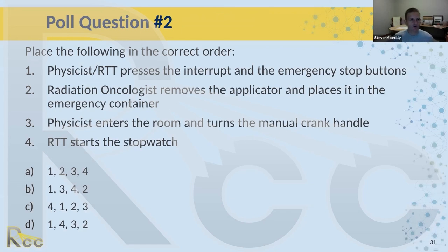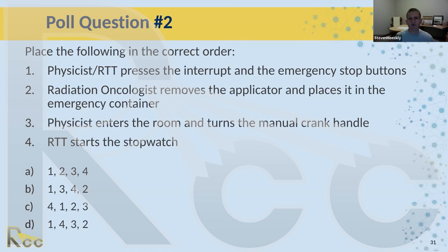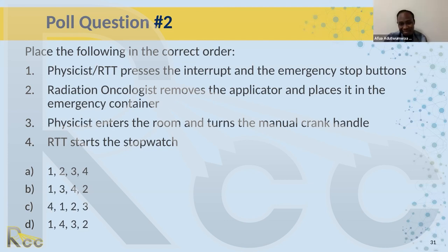Poll question two: place the following in the correct order for an emergency situation — A: physicist or radiation therapist presses interrupt and emergency stop button; B: radiation oncologist removes the applicator and places it in the emergency container; C: physicist enters the room and turns the crank; D: radiation therapist or nurse starts the stopwatch. Think about what order these things would happen in an emergency response.